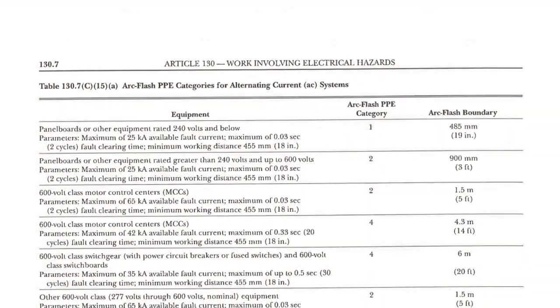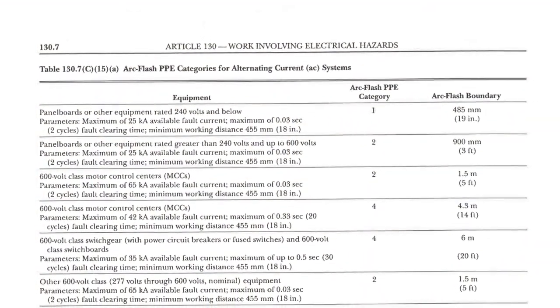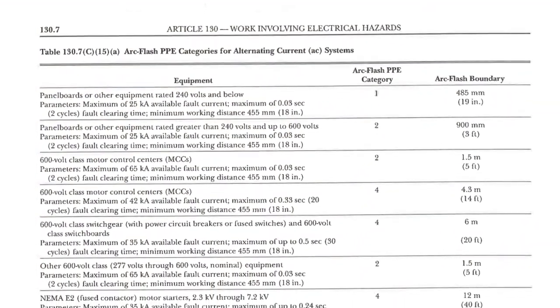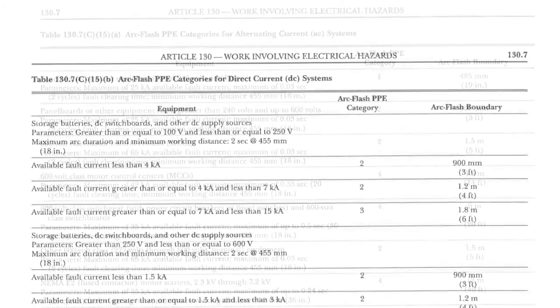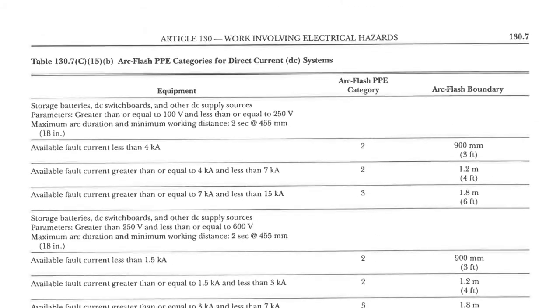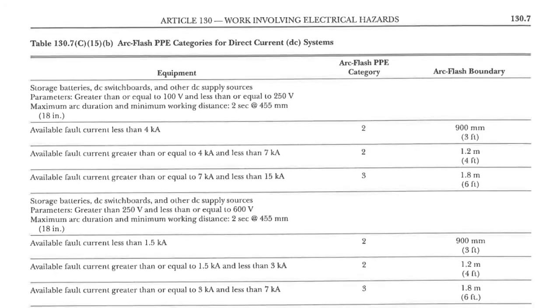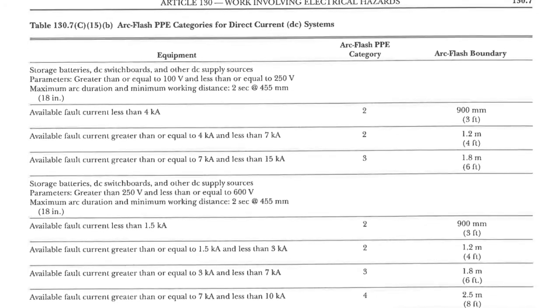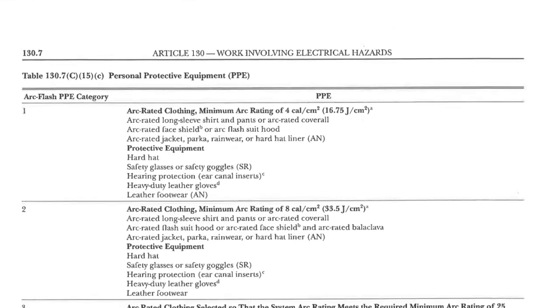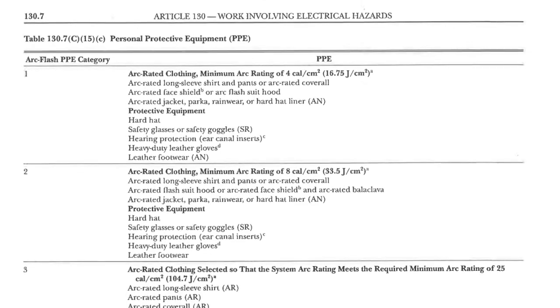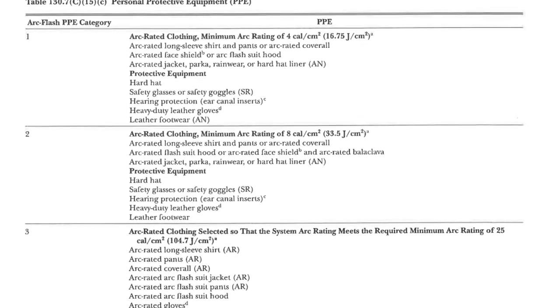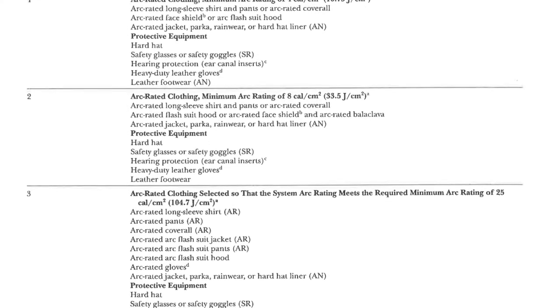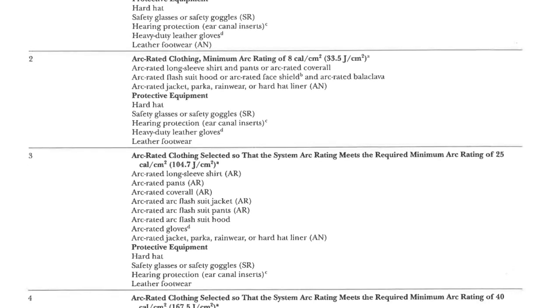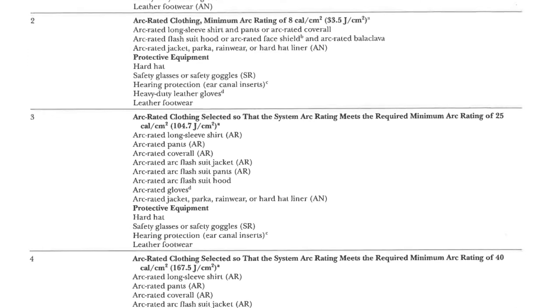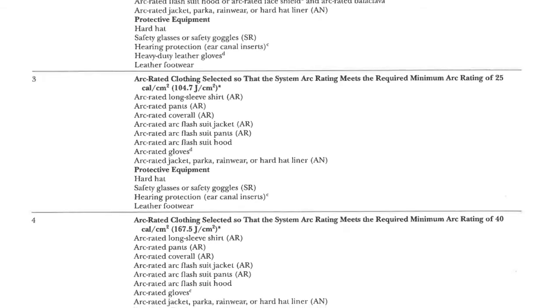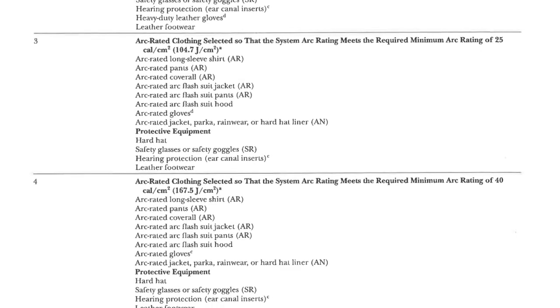Use Table 130.7(C)(15)(A) to identify arc flash PPE category for AC systems, or Table 130.7(C)(15)(B) to identify arc flash PPE category for DC systems. Once PPE categories have been identified, use Table 130.7(C)(15)(C) to list the requirements for PPE based on the arc flash PPE categories 1 through 4. This clothing and equipment shall be used when working within the arc flash boundary.